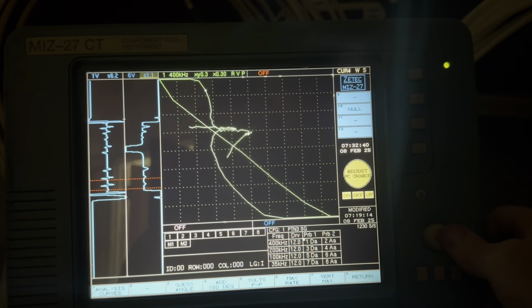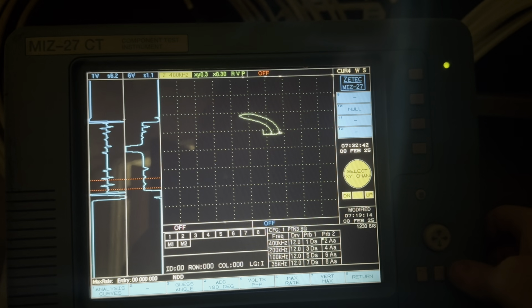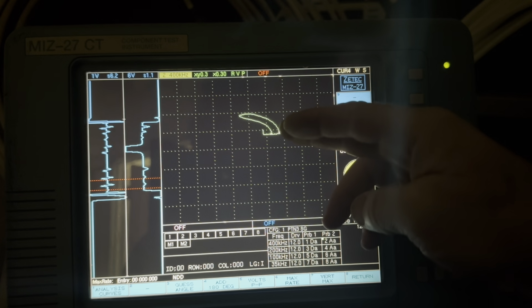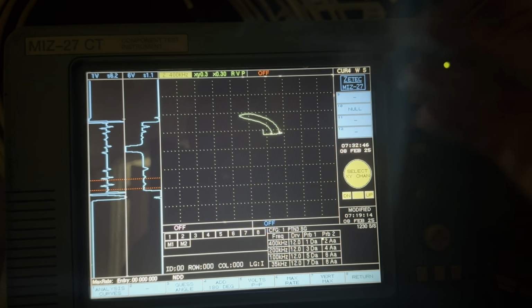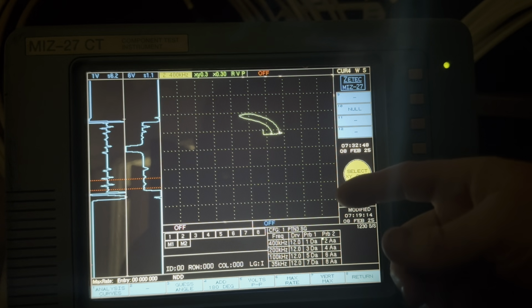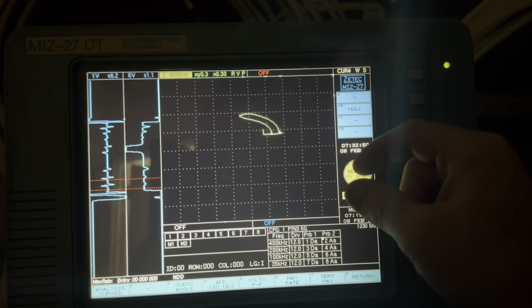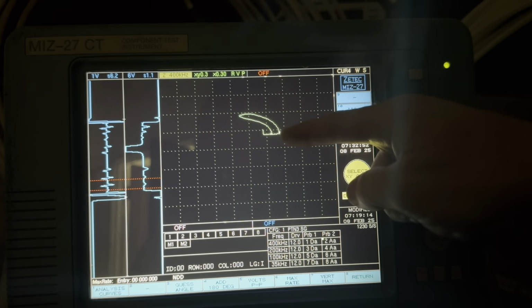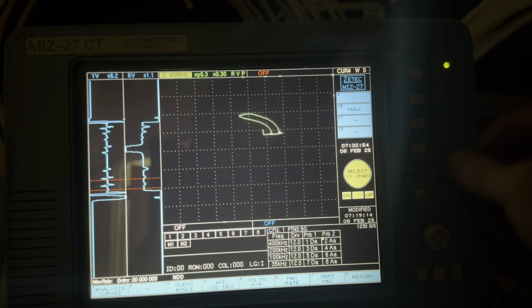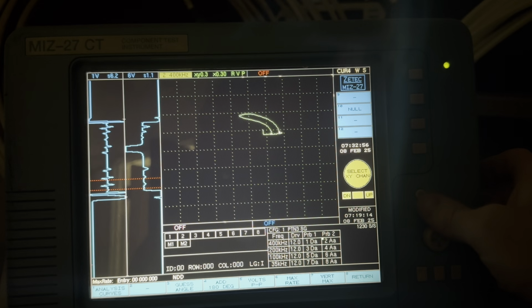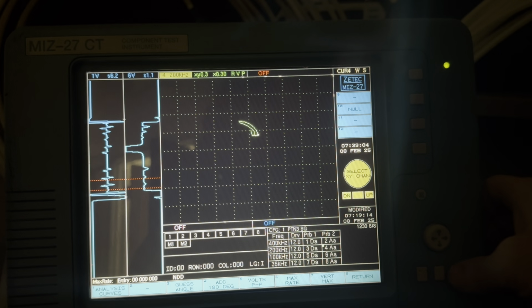Now, let's go to channel 2. Now, this is probably set to like 35 degrees. Some procedures will have you set the 100% hole to 40. Some will have you set horizontal noise, which is a small component here, to set that horizontal. That will give you clean strip charts and better detectability for flaws when you set noise horizontal. Channel 4, channel 6, they're roughly 35, 40 degrees.